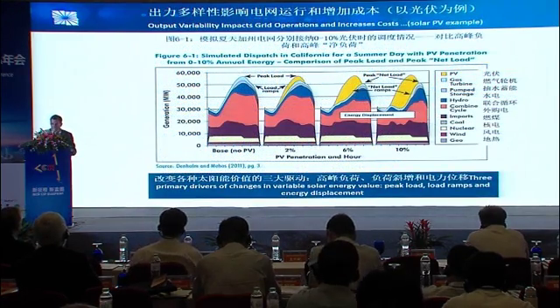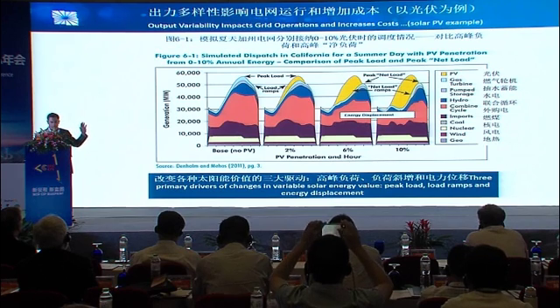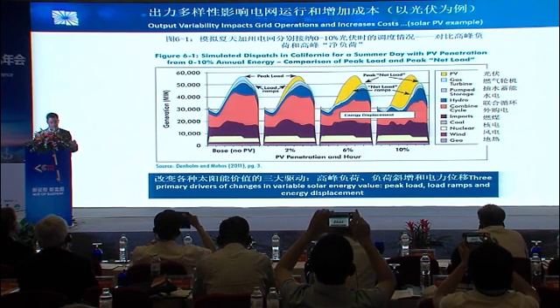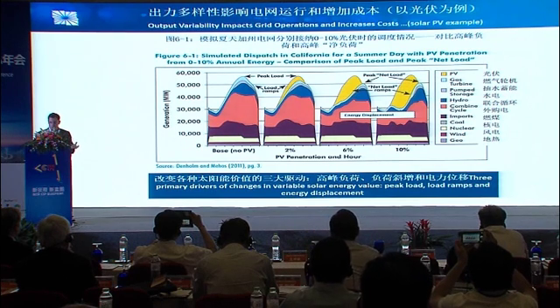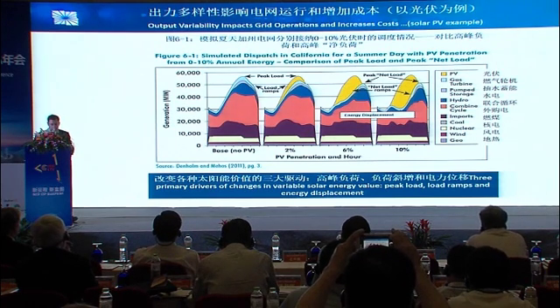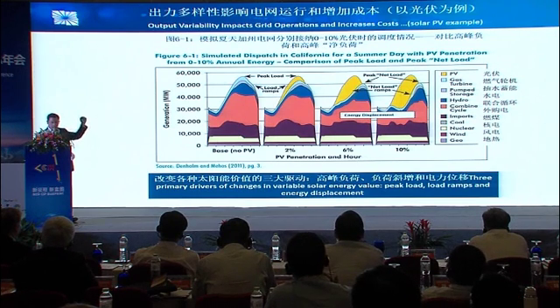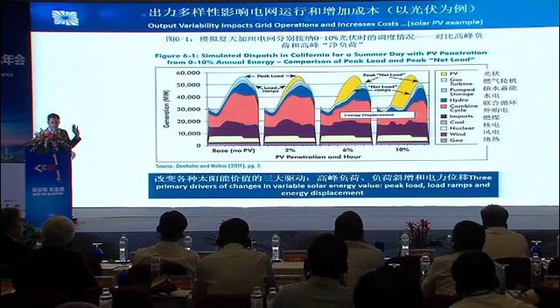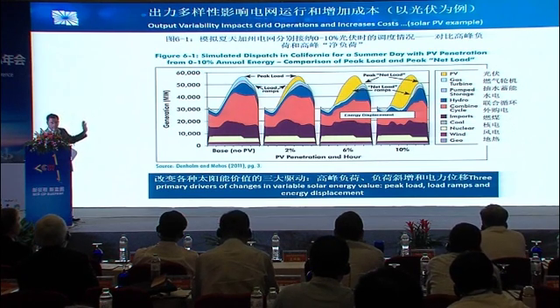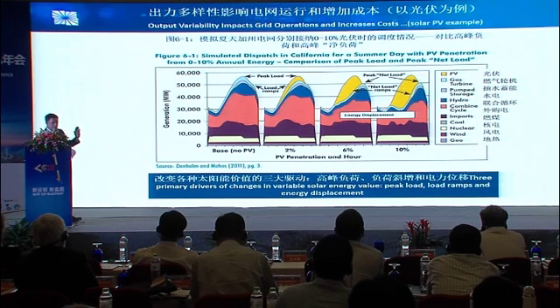One of the things people were predicting, now this is to show California, and it's looking at, over time, how does the load shape change from the perspective of the grid operator as you add more variable resources like wind and PV to the grid, in this case, as you add more photovoltaics. And several things happen. The peak load, the net load, which is the demand less the must-take resources the grid operator has to have on the solar, is changing and is becoming less. It's also shifting later in the day. In fact, the issue becomes, as you have a lot more PV approaching 10% on the grid, that your peak demand is now occurring when the sun's down.